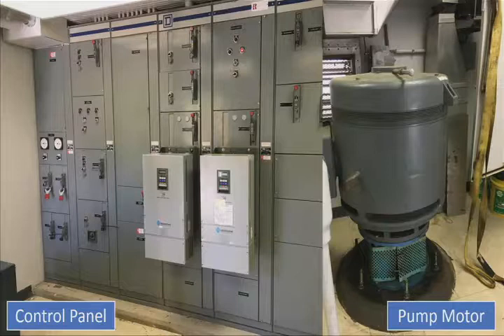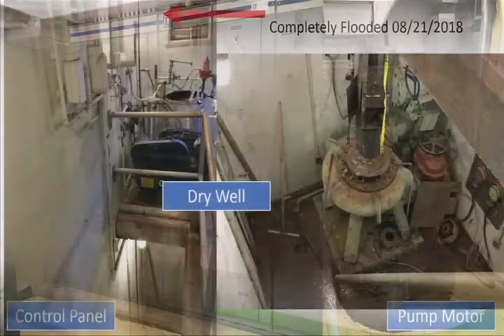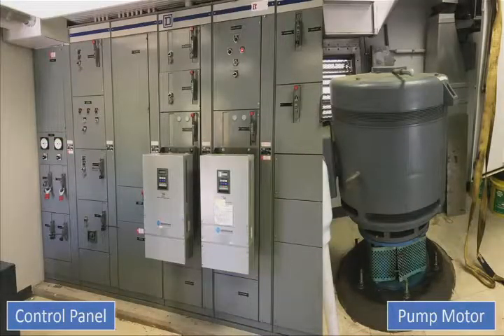Understood, okay. These are your pumps, your motor control center, and the variable frequency drives for these pumps. We changed our control schematics a little bit in 2006, I believe it was. We were doing some force main work, and we put in VFDs, variable frequency drives, which run a lot cheaper than the on-off 100 horsepower, bang, bang, bang. They continuously run, and they will ramp up or down according to the wet well level. If I have a lot of water coming in, I'm going to ramp up and pump a little more water. These things regularly pump 3,300 gallons a minute when it's raining hard.